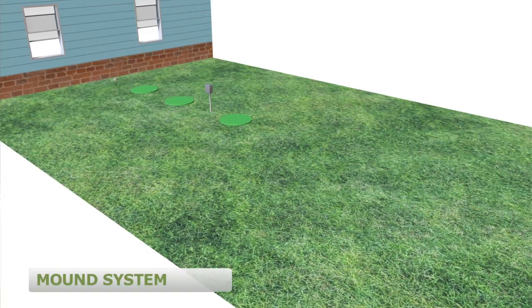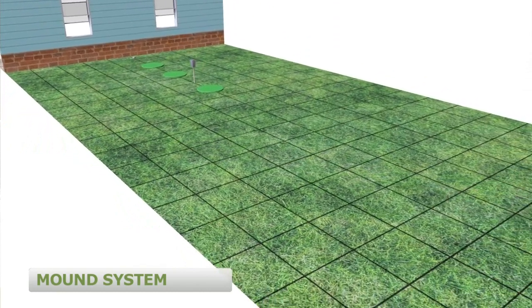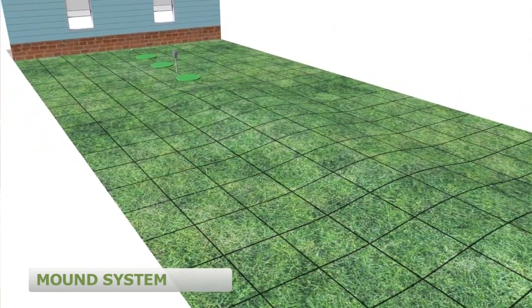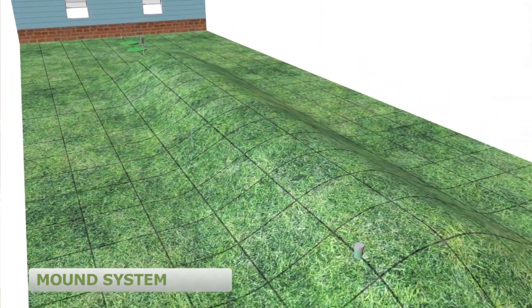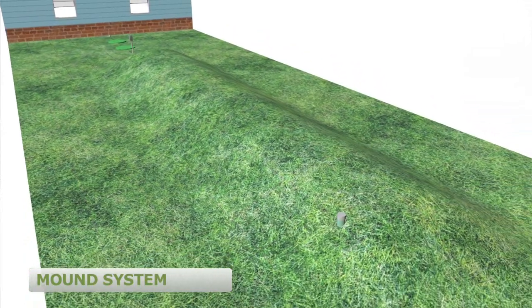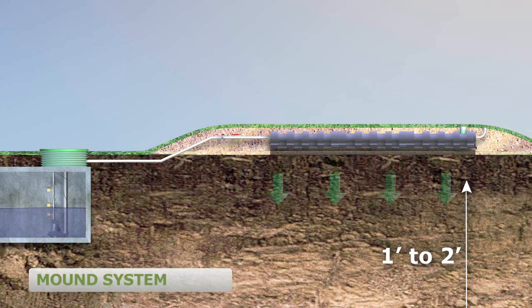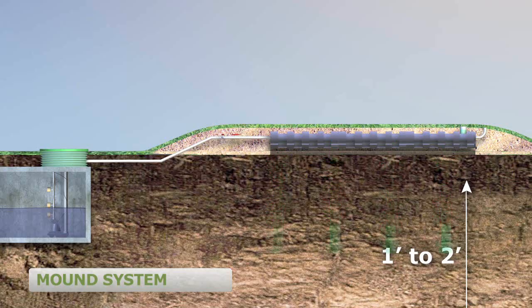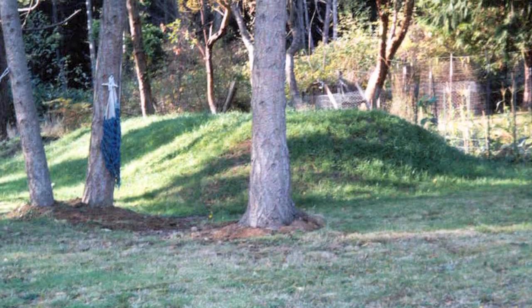Now let's talk about alternative systems. First, the mound system. Mounds can be used where there is only one or two feet of suitable native soil, because additional vertical separation is built up in a mound of specially engineered sand. The wastewater is applied at the top of the mound and percolates down through the sand to the native soil below.